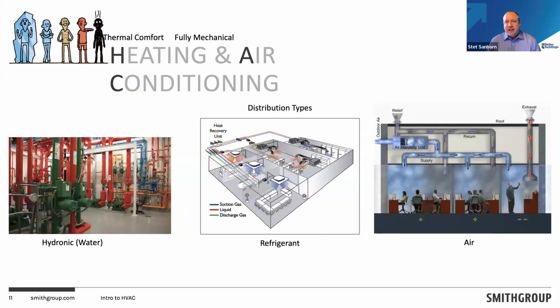So I want to give you a sense of the flavors, because heat pumps come in a whole host of menus, and not all heat pumps are created equally. The type of heat pump application you might have in your building really depends on how you move heating and cooling energy around your building. There are 3 major categories. Hydronic is often considered the old-school way of moving hot water or chilled water around your building, but it's definitely most common in larger commercial buildings where you might have what's called a 4-pipe system: hot water source and return, and chilled water source and return. Those hydronic systems mean that your heat pump is likely standalone. It's a monoblock, an enclosed system, and it sits maybe in a mechanical room, on a roof, or out on a pad.